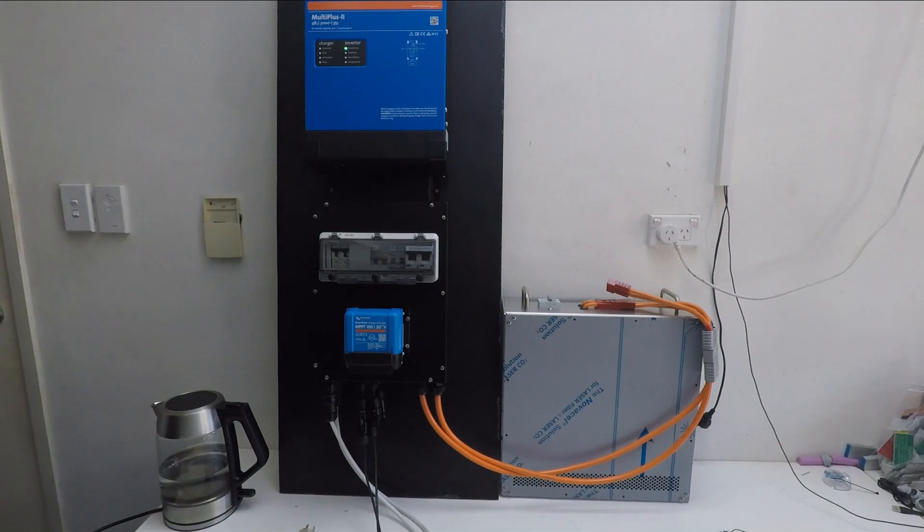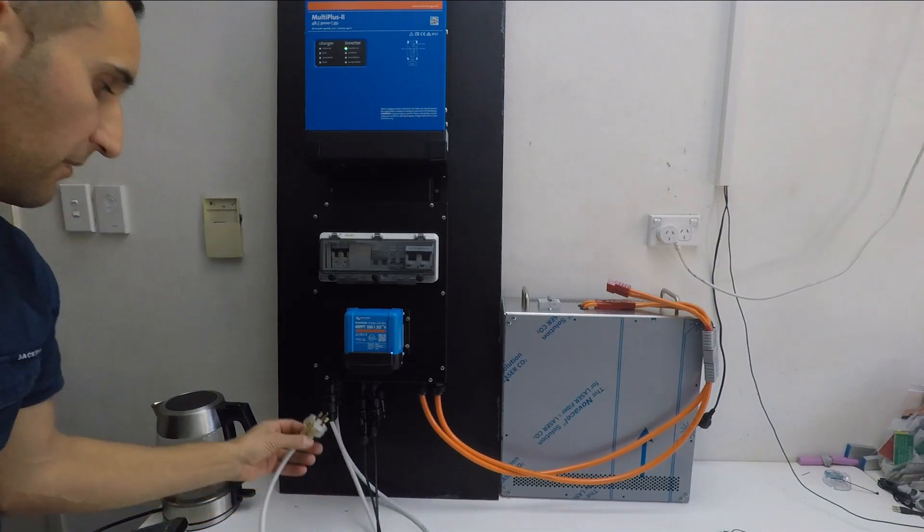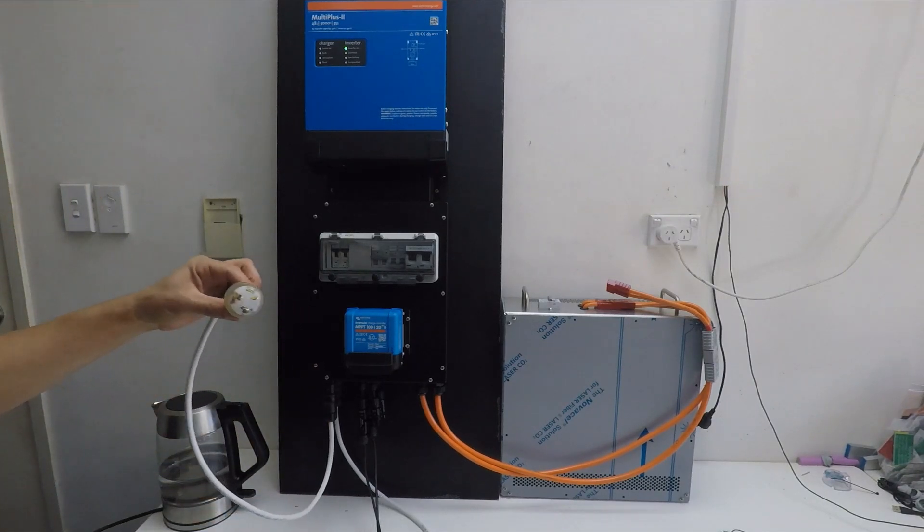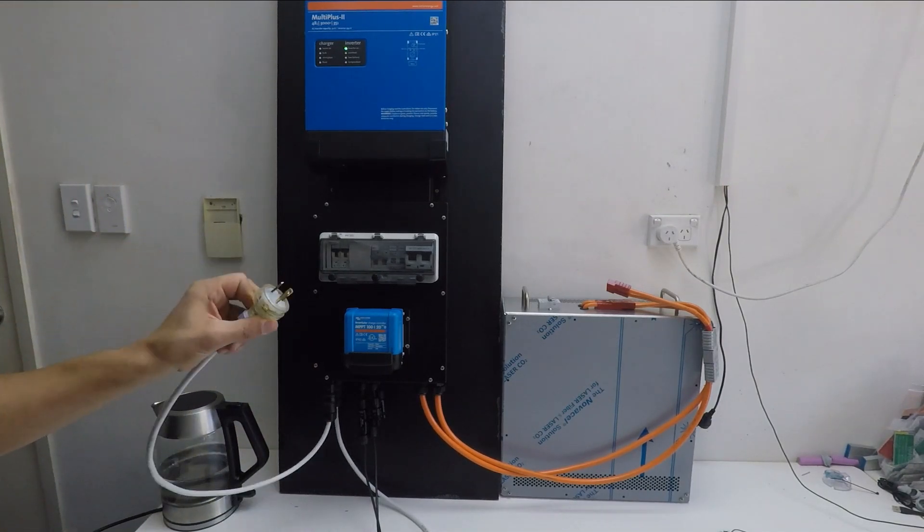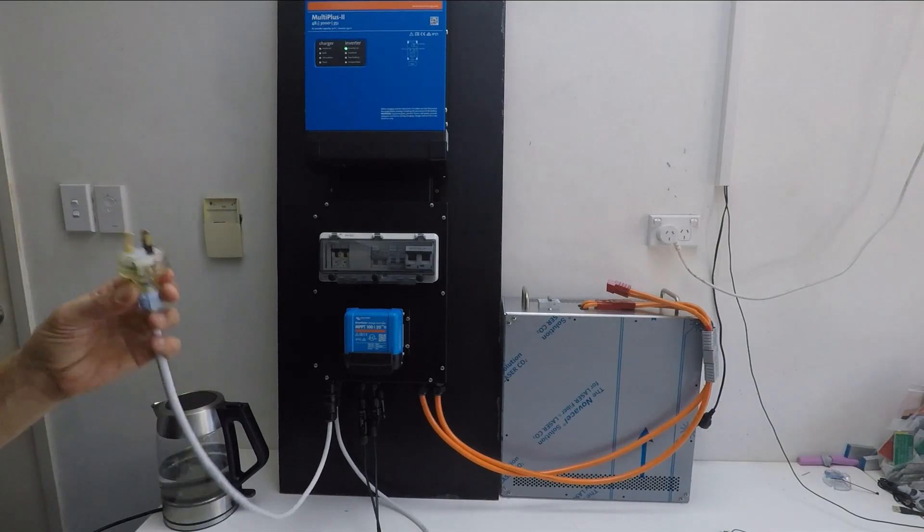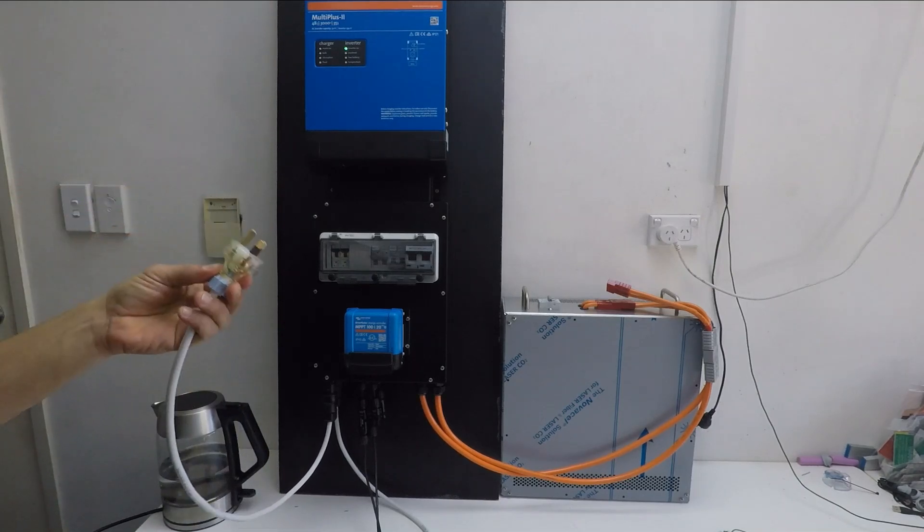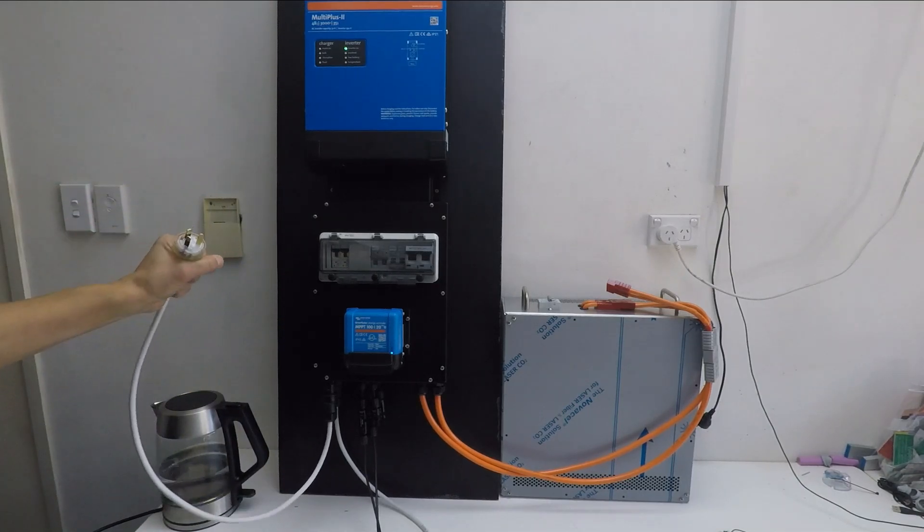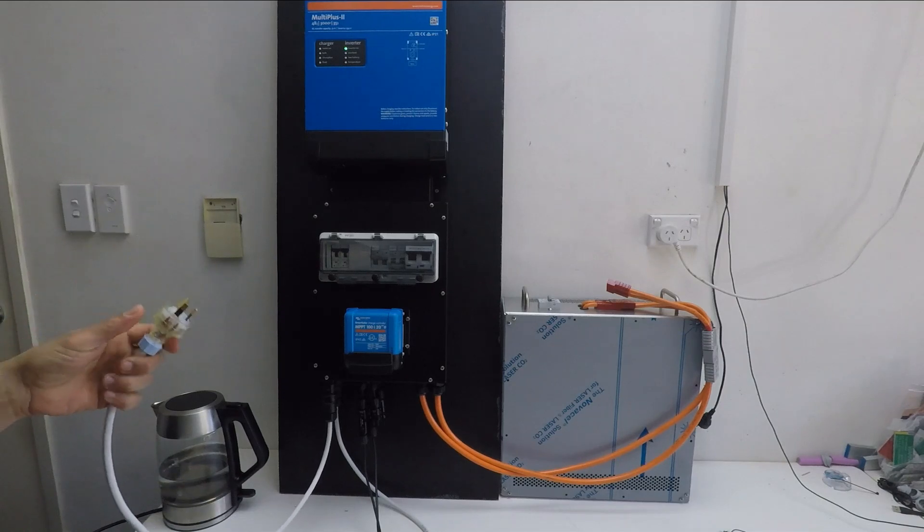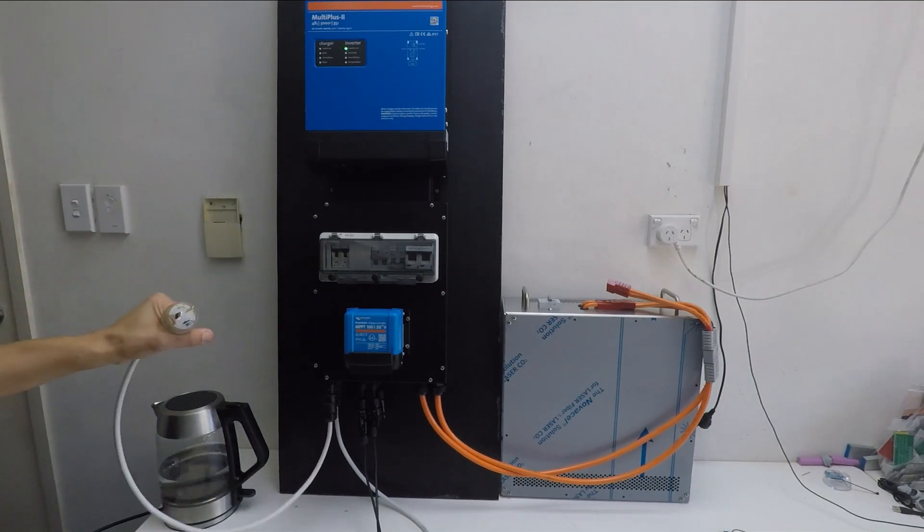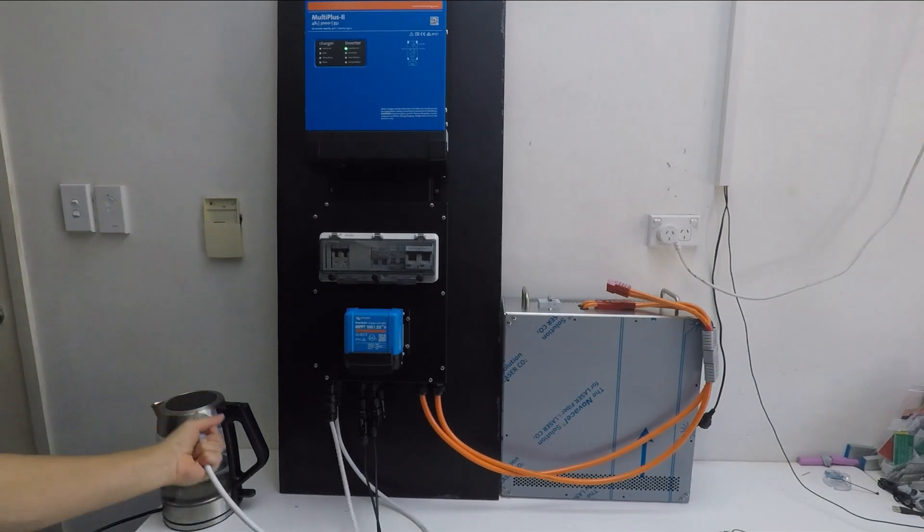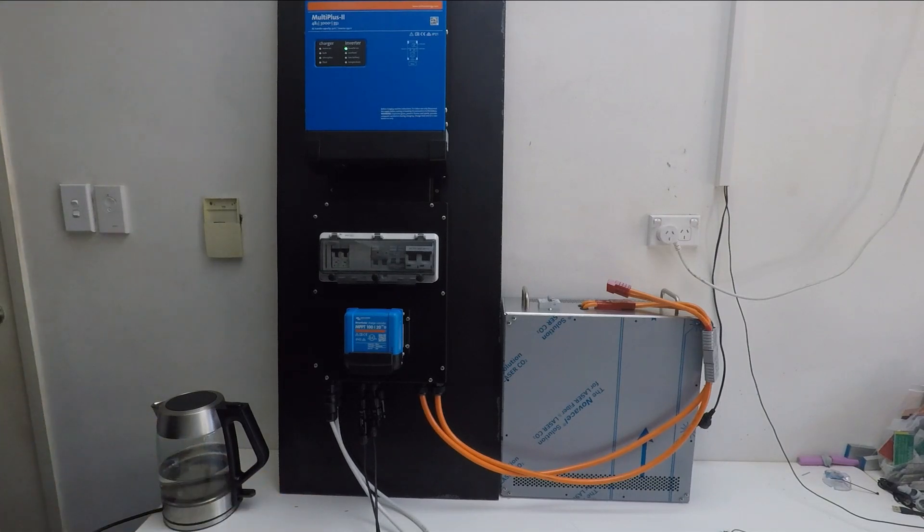OK, now we're going to show how to charge a unit from a generator. That's a very simple operation to charge. At the moment we've got our test lead. As I mentioned before, this shouldn't be used permanently, this is only a test lead. Your electrician should hardwire this to your generator, so that these pins cannot be touched while the unit is on. This is for testing purposes only.